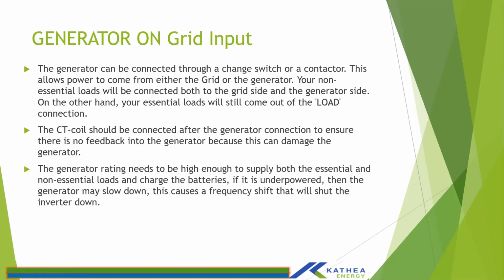And then when you're connecting the generator on grid input, as I've said, you can connect it through a changeover switch or a contactor. A changeover switch is basically there to make sure that there is only one source of power, that is generator or grid, supplying the system. So it's either grid or generator, not both. So you can connect the generator through a changeover switch, and then the setup will still be the same as when you're using a generator as a grid input.